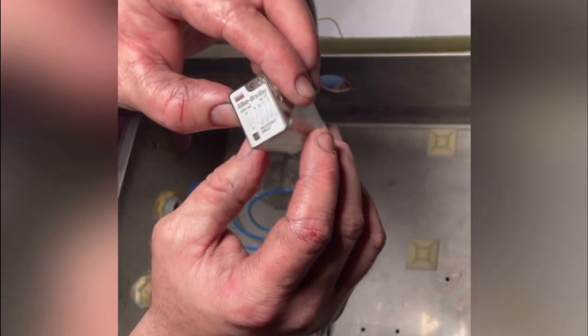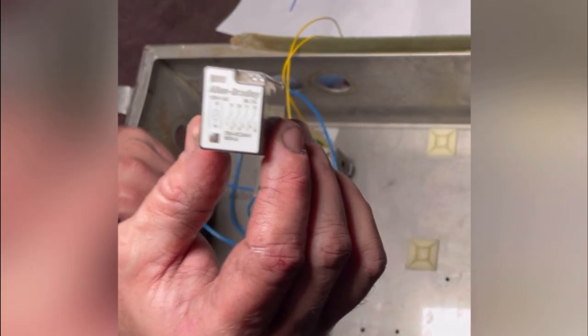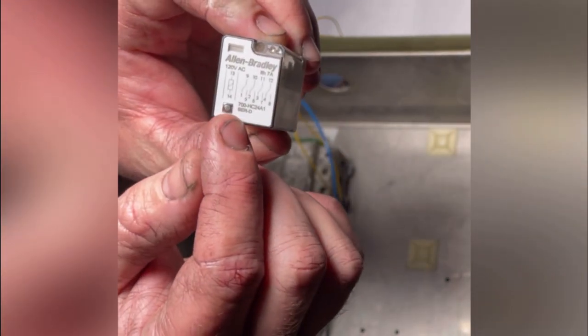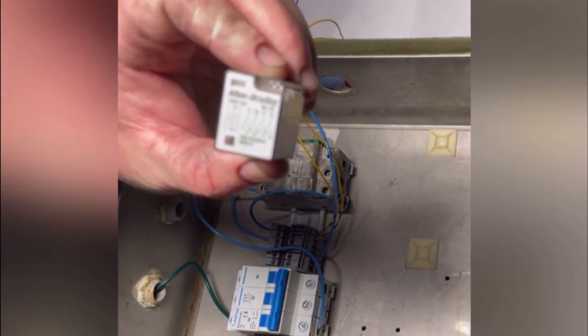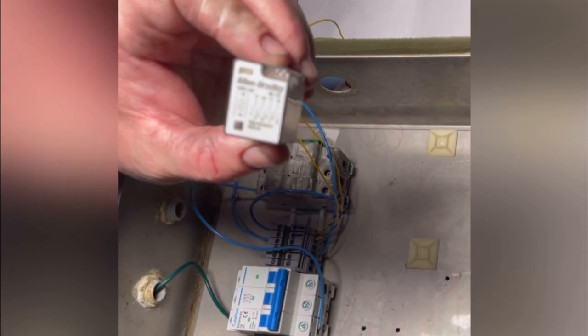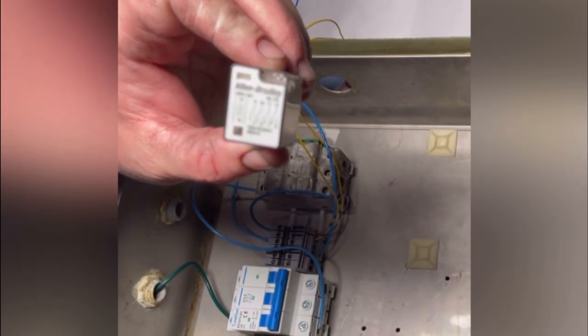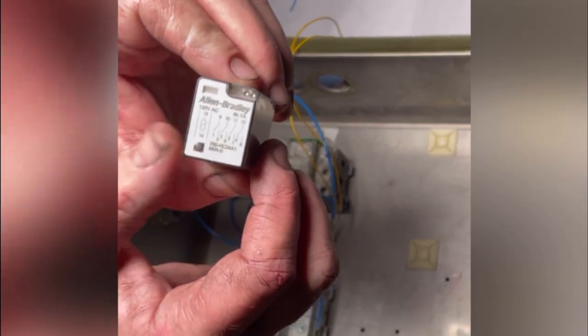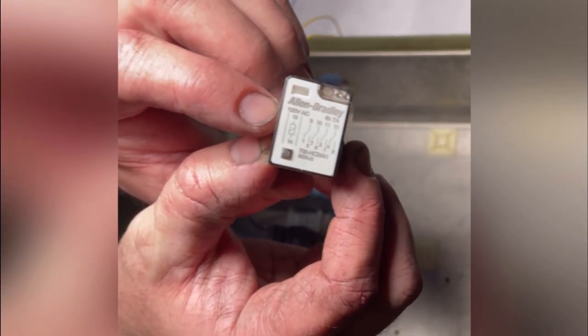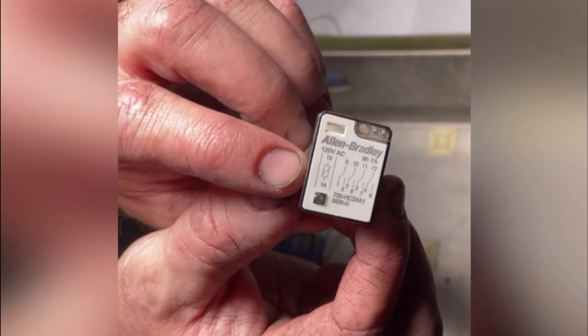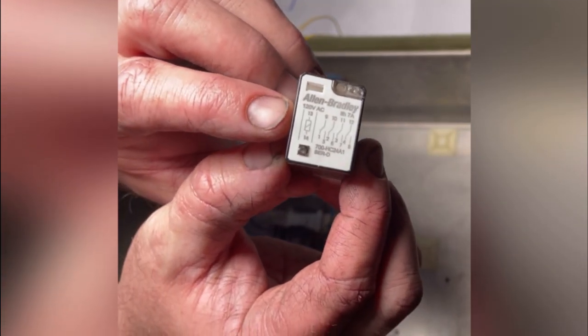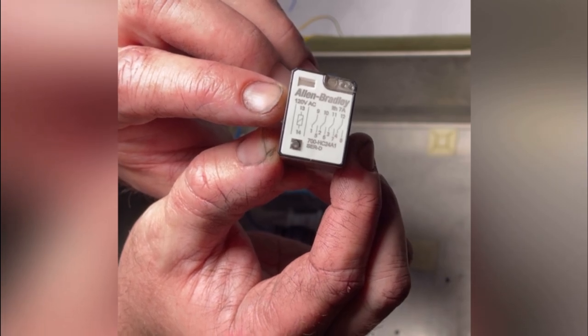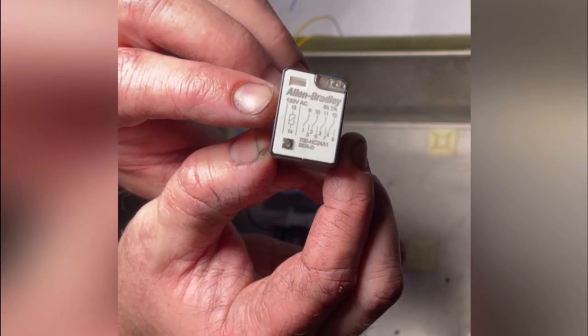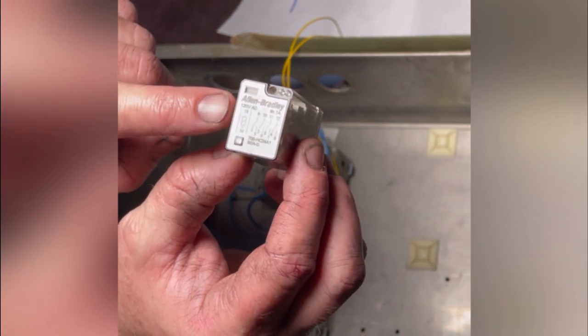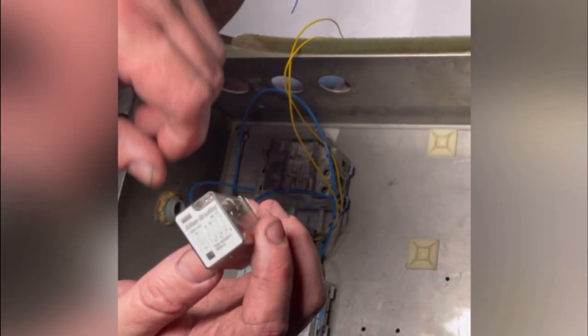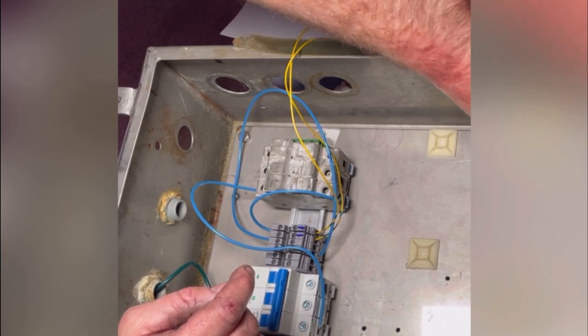It's something that we turn on and off. The way that relays work is you turn the relay on and off, and it has sets of contacts. Think of a light switch. You flip a light switch, and that's like turning a relay on, and then it's going to either close or open sets of what we call contacts. If you can see this, 13 and 14, that's the coil. You always want to verify you got a 120 volt AC coil. So we're going to run our hot to 13 and our neutral to 14, and that's going to be our first load. Let me wire this up and then we'll demonstrate it.